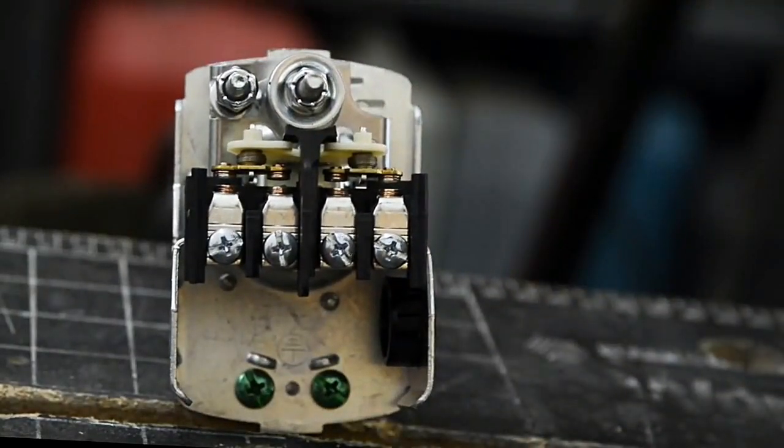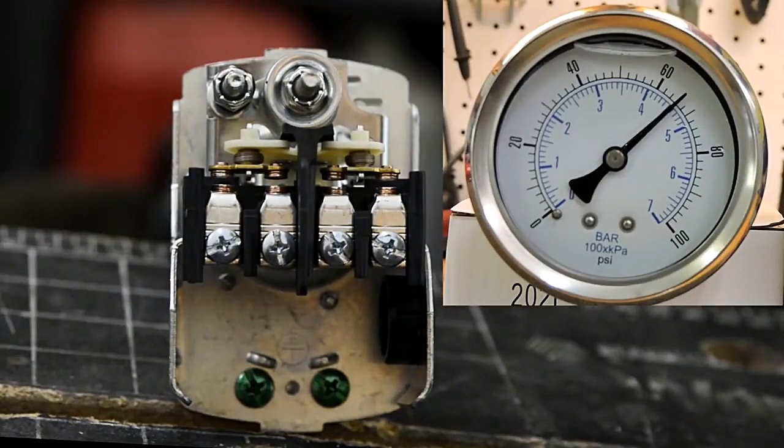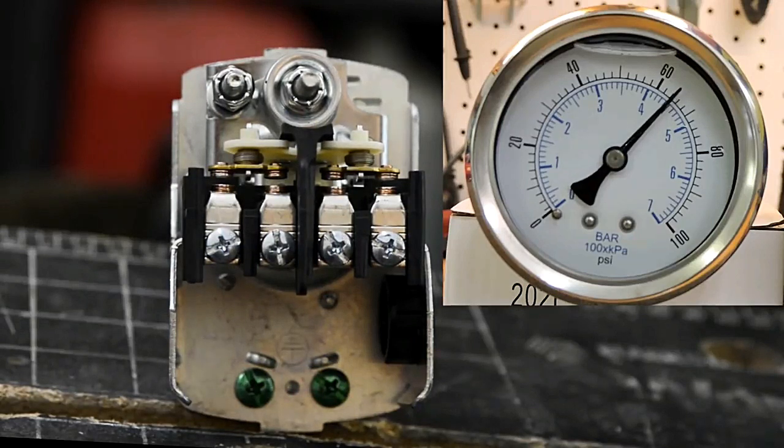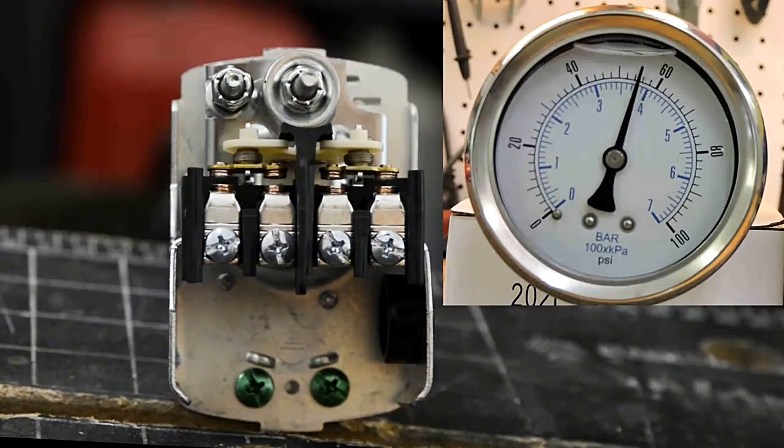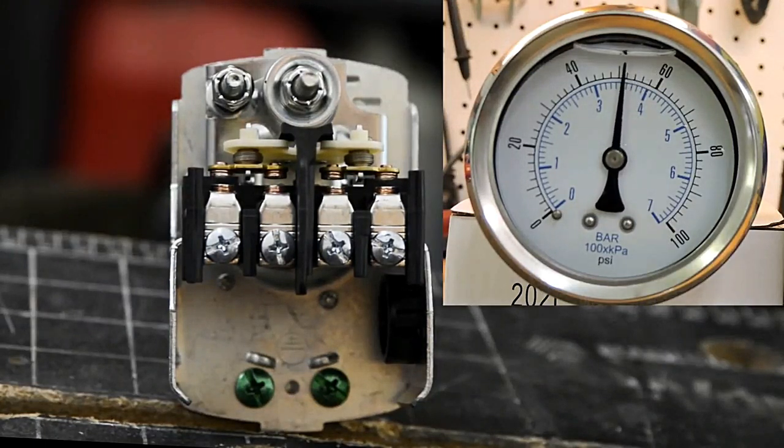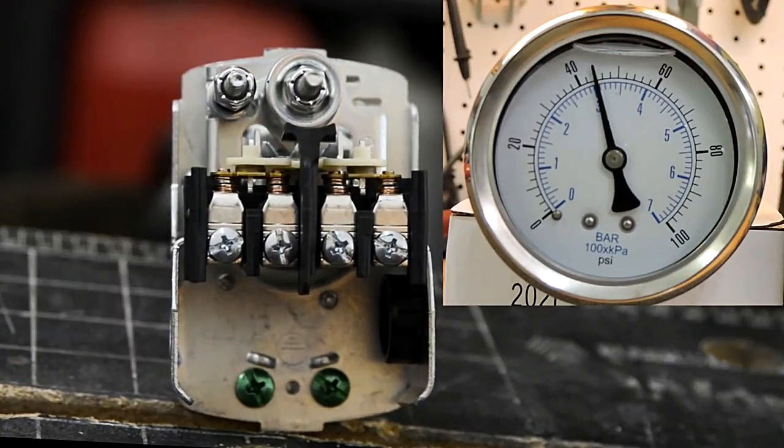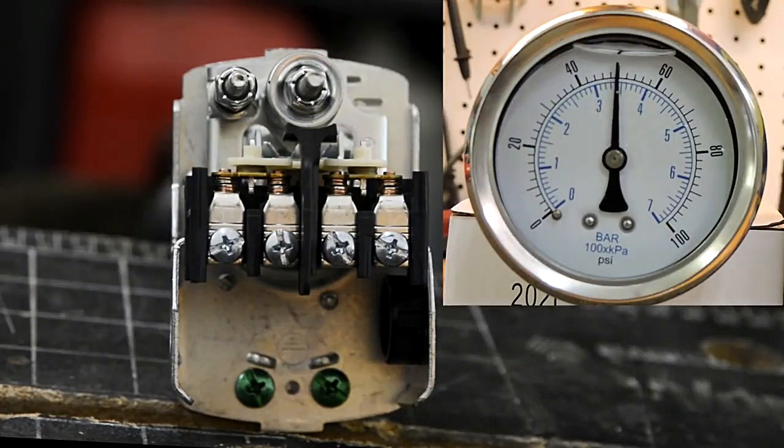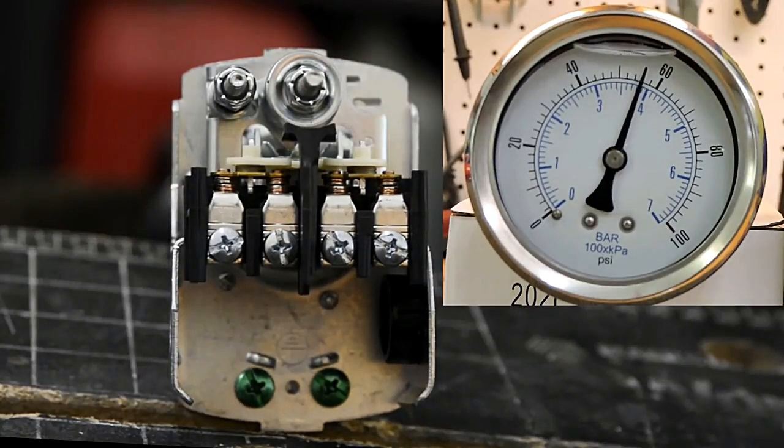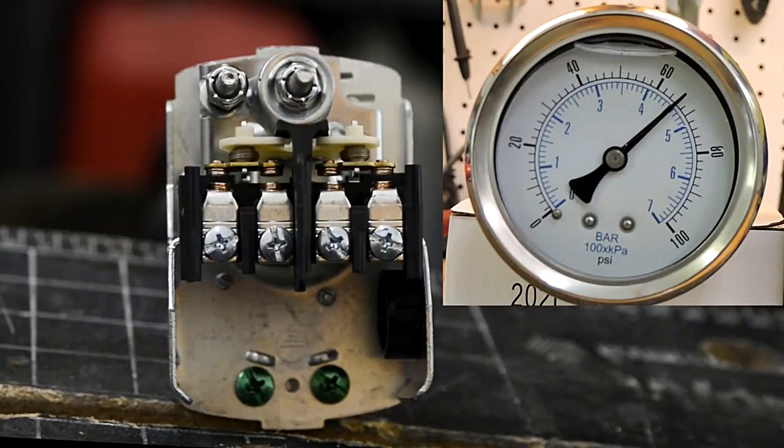We're going to show you the contacts opening. The contacts are open now because the pump will be turned off. The pressure has been satisfied. So as we lose pressure, the contacts will close. Now the pump is running until the pressure is satisfied again. So the pump is running, the pressure is increasing until it reaches the cutoff.